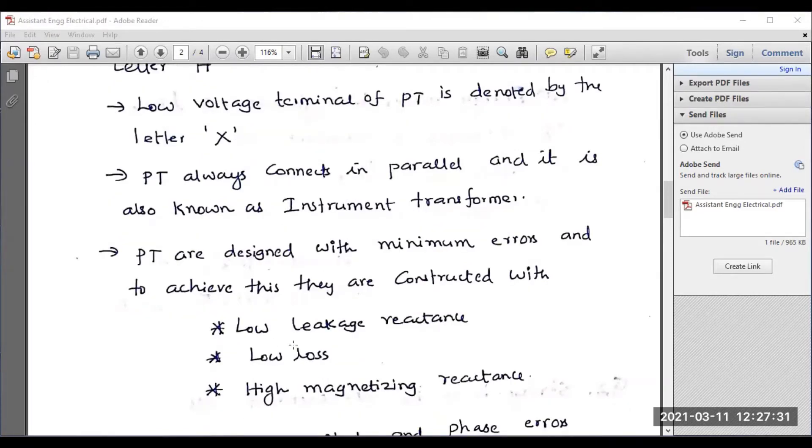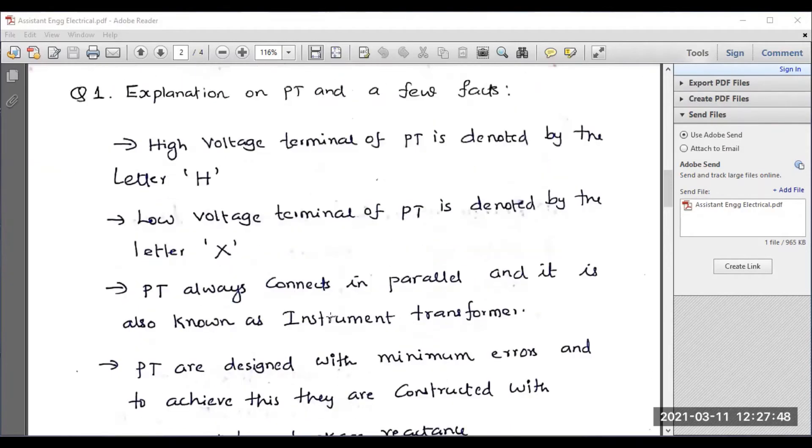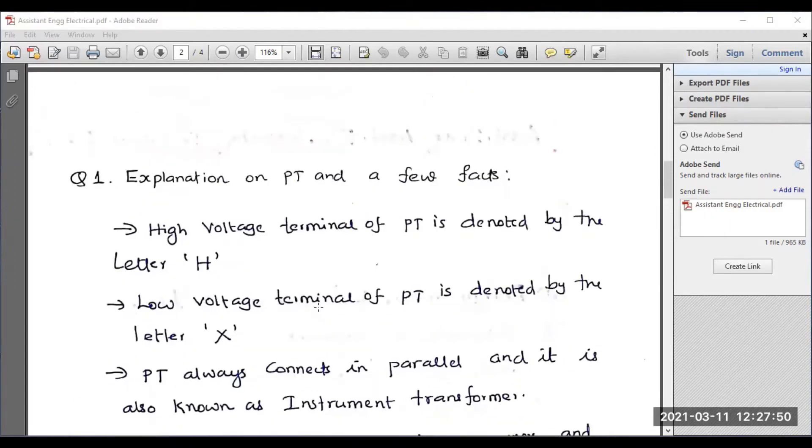The following points need to be considered: low leakage reactance, low losses, high magnetizing reactance. These points will be considered while designing the PT. Normally, magnitude and phase errors are the commonly occurred error in potential transformer.